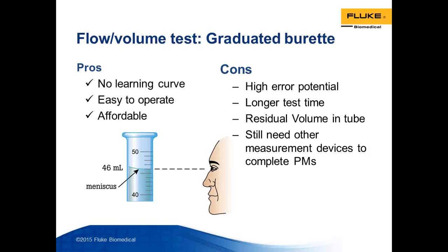It takes a longer test time versus other methods. There is residual volume you have to be aware of when you're doing the testing with the burette and stopwatch. And finally, you're not just done there, right? There is a manual calculation you need to do. You still need to write the results down. And you still need other measurement devices to complete the PM. You're going to need a pressure gauge to include in the testing. So it's a labor-intensive method, simplistically put, in terms of the time and the attention required to complete the testing for performance verification.